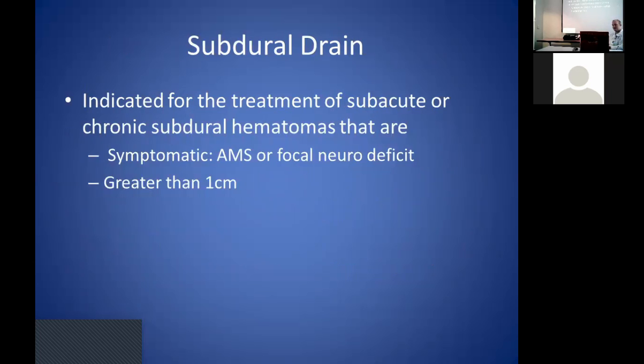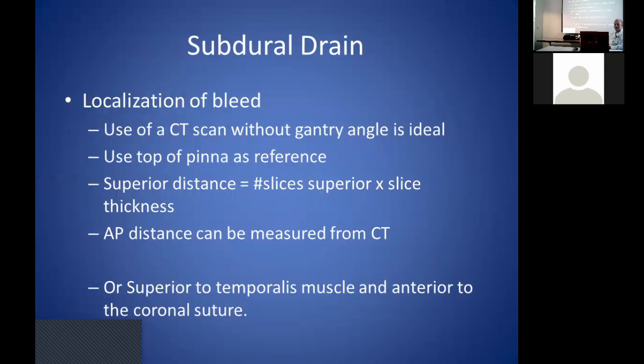These are indicated for the treatment of subacute or chronic subdural hematomas that are both symptomatic, meaning with altered mental status or a focal neurologic deficit, and greater than 1 centimeter in thickness. Now, to localize the bleed, you use a CT scan of the head. Although generally when you're doing neuroimaging you prefer a gantry angle appropriate through the typical plane, a gantry angle of 0 is preferred in the localization for a subdural drain.